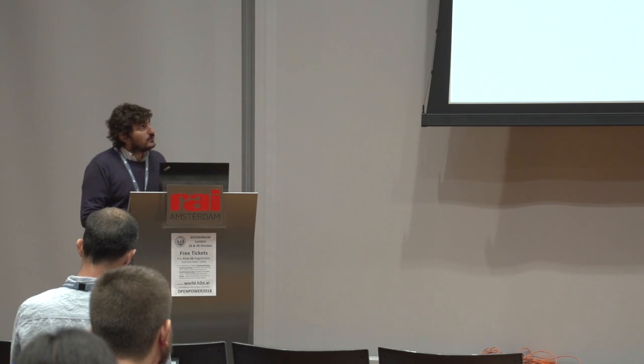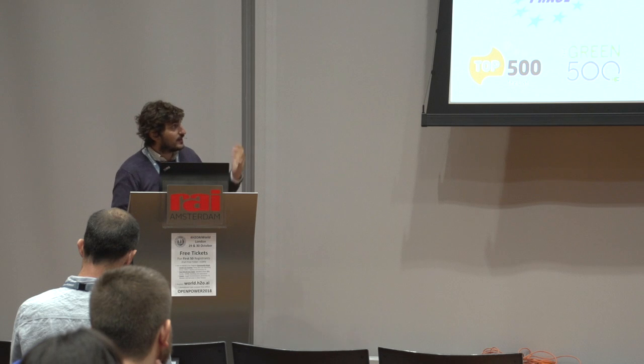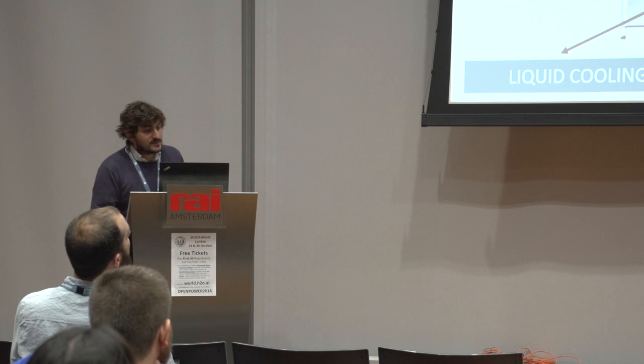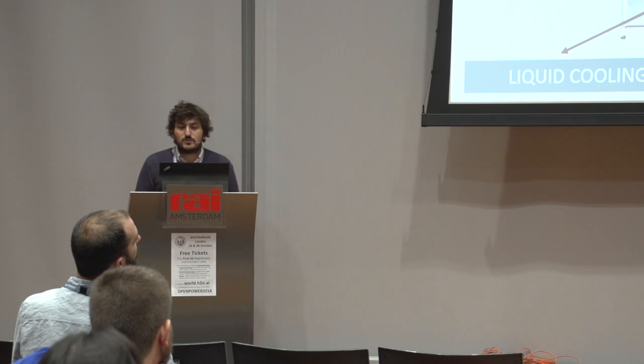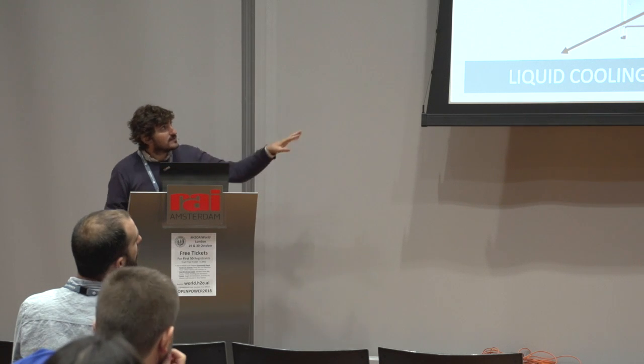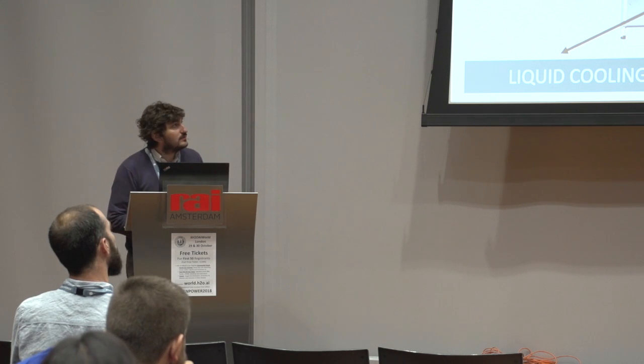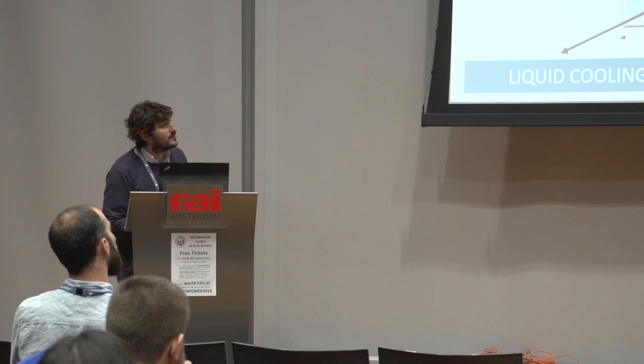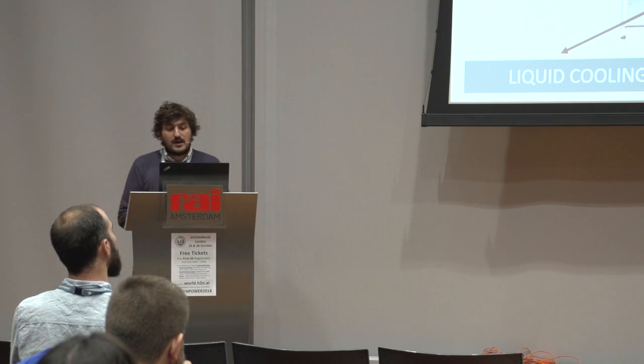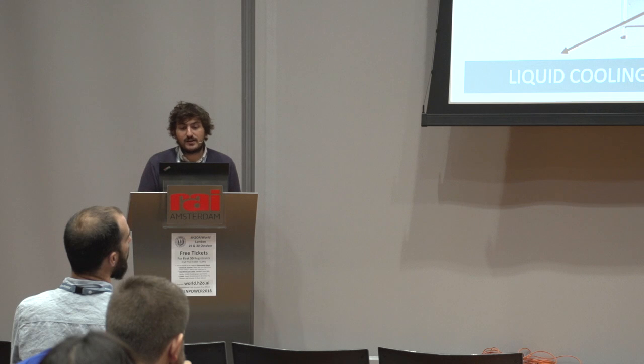So let's see how we do it on the Davide system. The Davide system has been installed last year in Cineca in Italy and has been ranked in the Top500. It's an OpenPOWER system based on the IBM Minsky system. It has two POWER8 sockets and four NVIDIA P100 GPUs, it is liquid cooled, and it has an additional board component designed at the University of Bologna in collaboration with ETH Zurich to improve the self-awareness of the node and to enable fine-grained power and performance monitoring and analytics on the node itself.